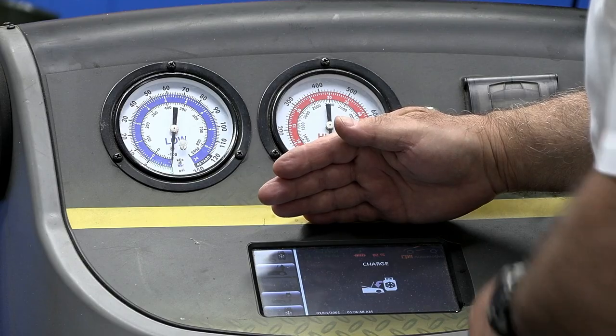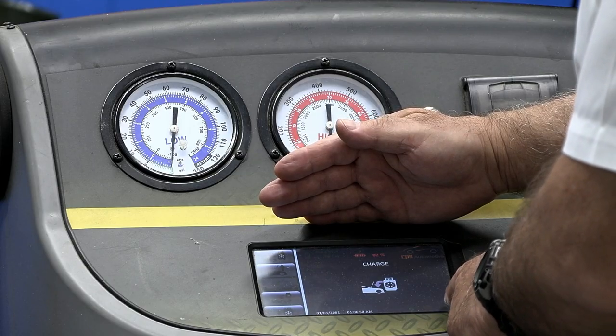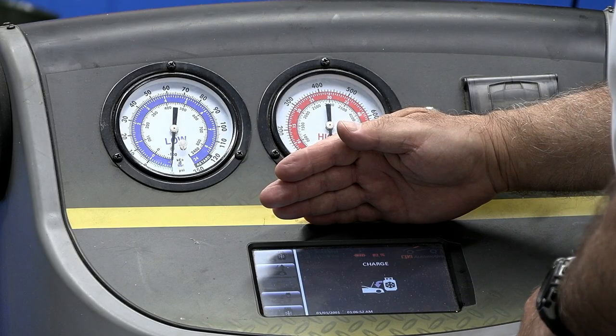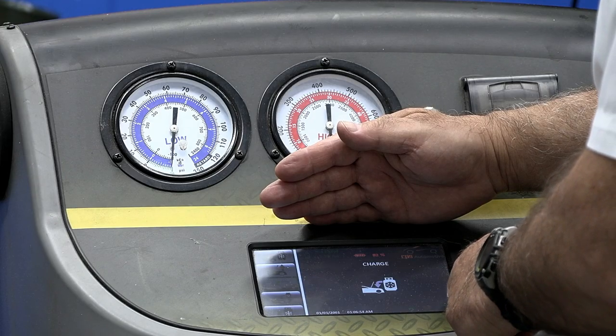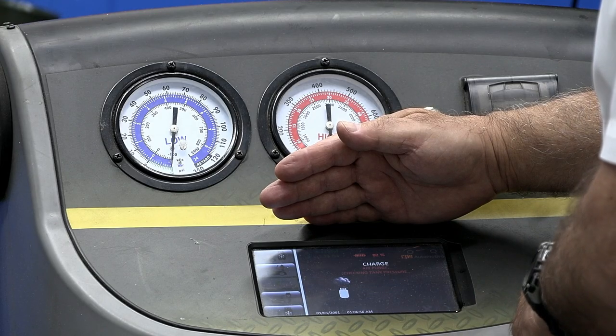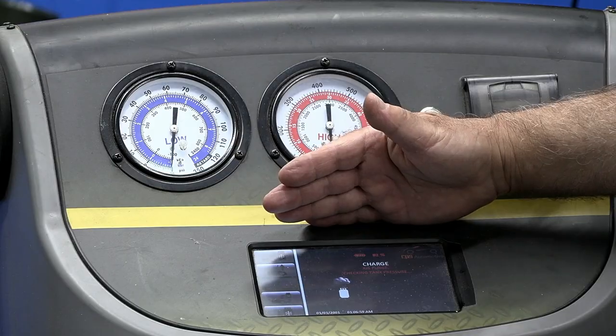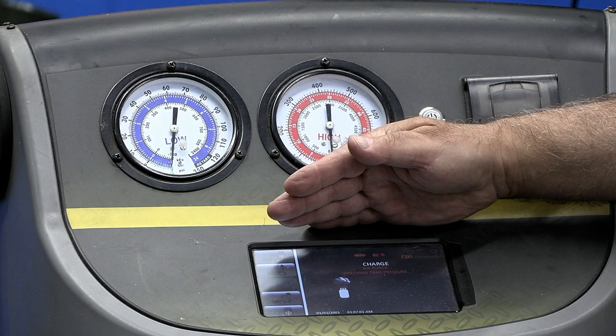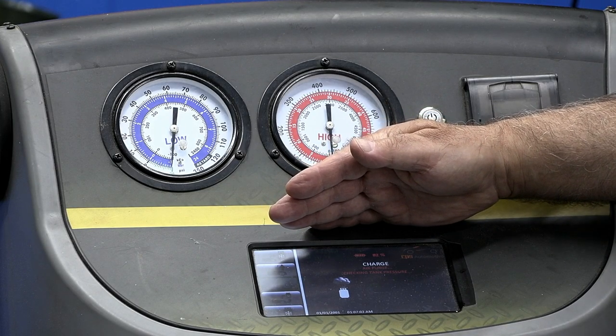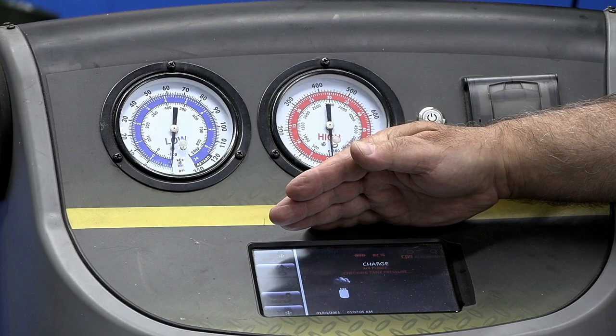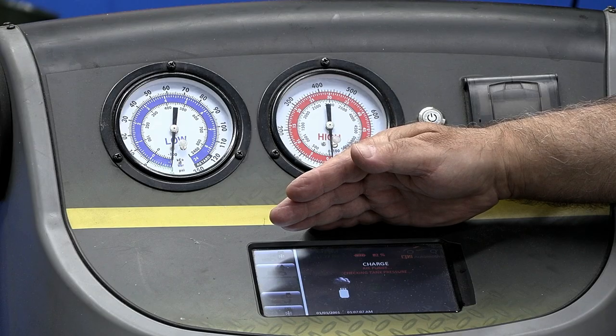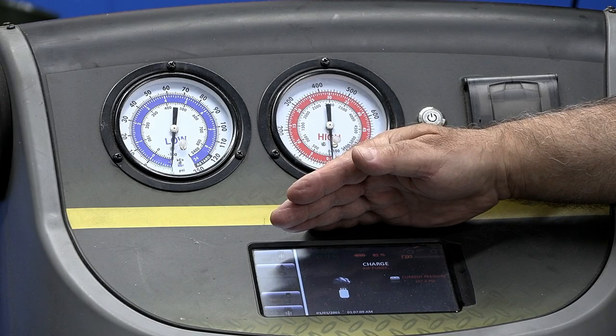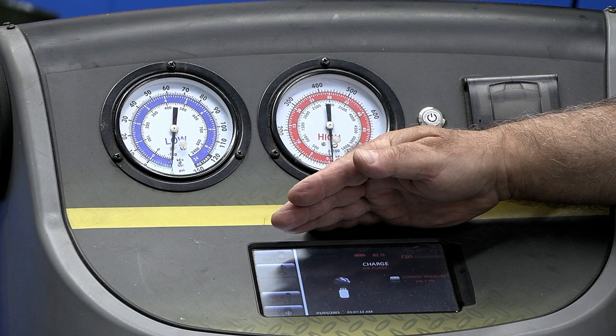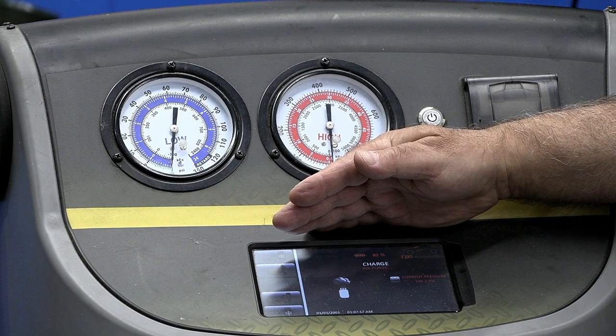So now I go charge, and I wanna hit this button here. Now it's gonna clear the tank. You're gonna hear like psh, psh, psh, these are automatic air purges. If your machine does not have automatic air purge, you're gonna have to look at the pressure in the machine on the side of it and manually hit the button to get the air out. Most new machines are all automatic.